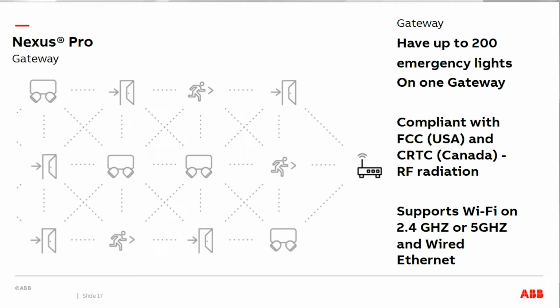This drawing does a good job of showing how all of the fixtures communicate with each other. Every single fixture acts as a transmitter and a receiver. So if our sign in the bottom left corner were to have a fault, whether a charger failure, the battery not discharging properly, or one of the lamps burned out, it will send that signal to all of the fixtures nearby, making sure every fixture can see has that information.